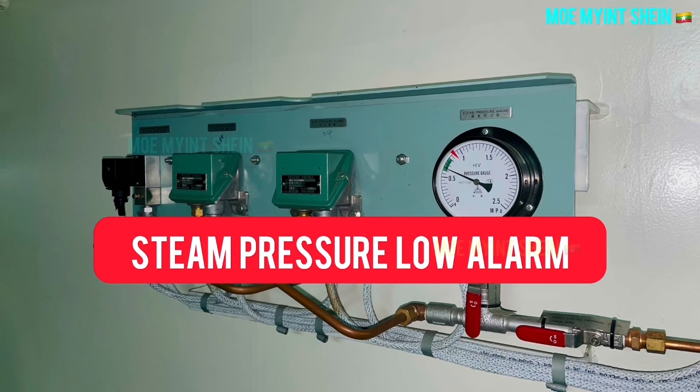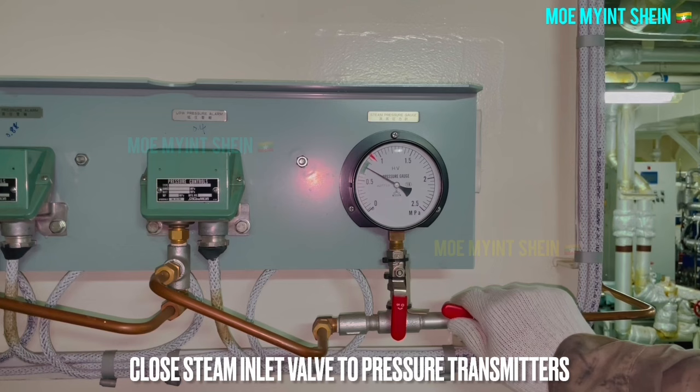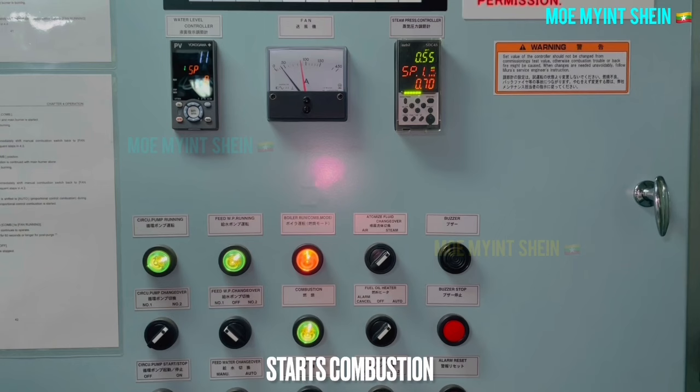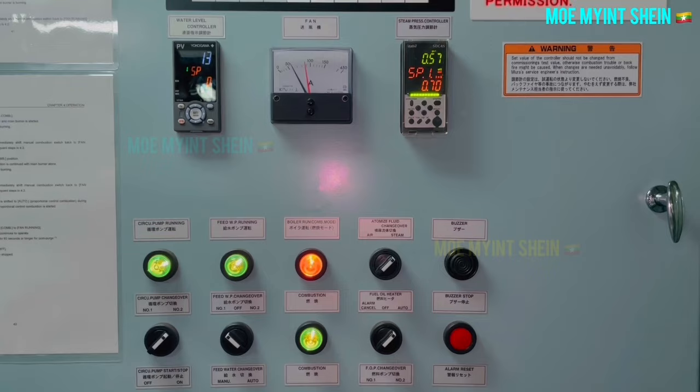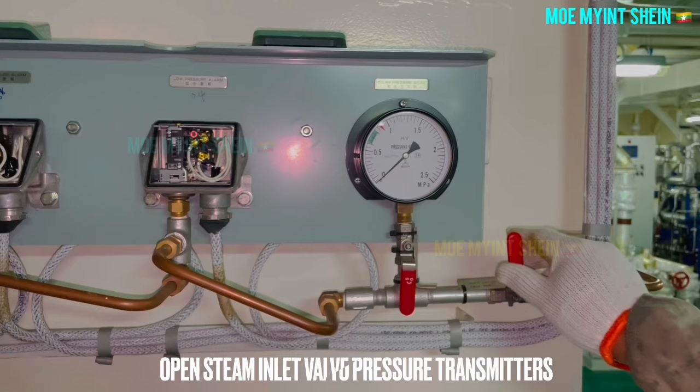Okay, let's test the steam low pressure alarm. At first, close the steam inlet valve to the pressure transmitters. Carefully open the drain plug of the steam manifold. At this time, ensure the boiler is in combustion. The low pressure lamp is going to activate as you slowly open the drain valve of the steam manifold. Before resetting the alarm on the panel, close the drain valve and open the inlet manifold valve.